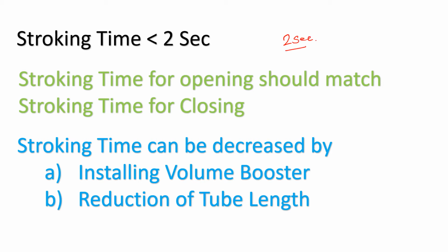Now, for a good design, the time for the opening and closing should match. I mean that if the opening time is 2 seconds, the closing time should be near to 2 seconds, or at max it can be 3 seconds. But if the opening time is very less compared to the closing time, that may result in oscillation in the control loop, or proper tuning in such cases is not possible. So it is always avoided to have a very different stroking time for opening and closing.